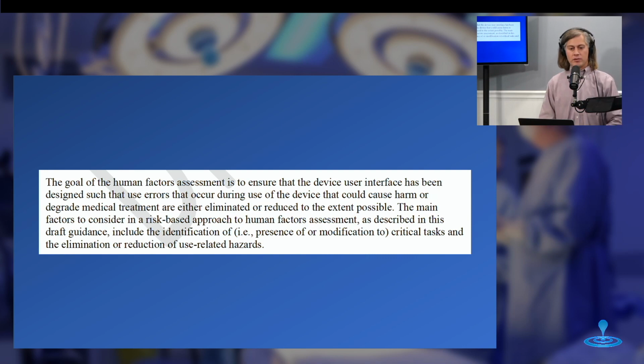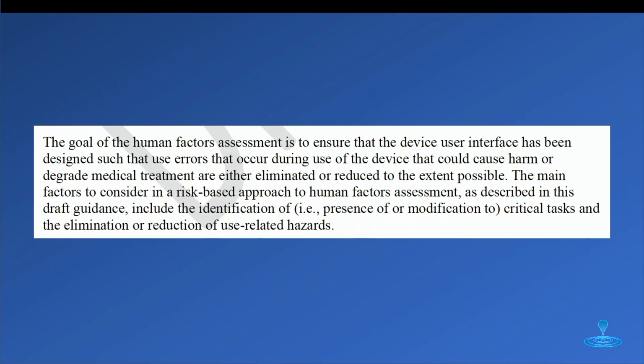FDA says the goal of human factors assessment is to ensure that the device user interface has been designed such that use errors that occurred during the use of the device that could cause harm or degrade medical treatment are either eliminated or reduced to the extent possible. The main factors to consider in a risk-based approach to human factors assessment, as described in this draft guidance, include the identification of critical tasks and the elimination or reduction of use-related hazards. So they're saying the real focus here is risk. We want to eliminate risk, not just device risk by itself, but use risk as we interface with the device.